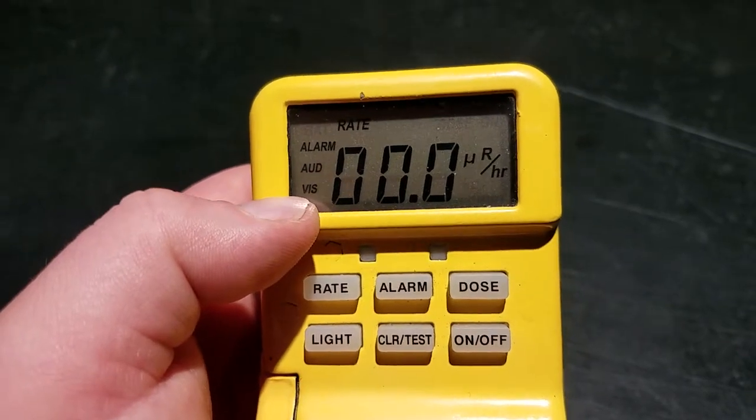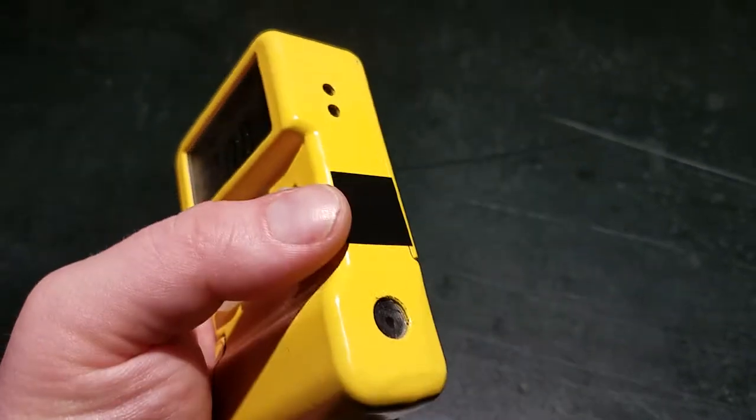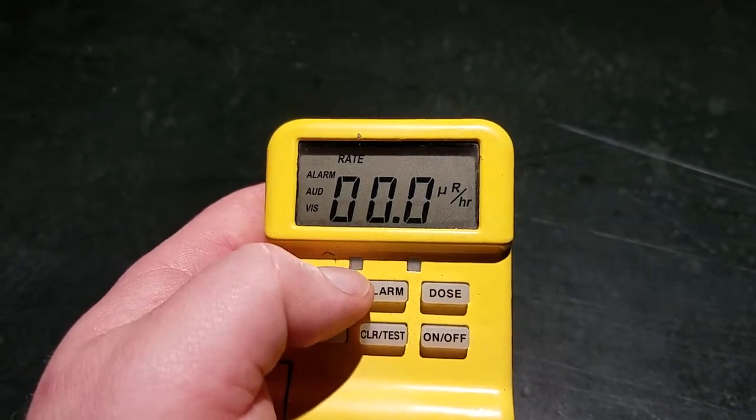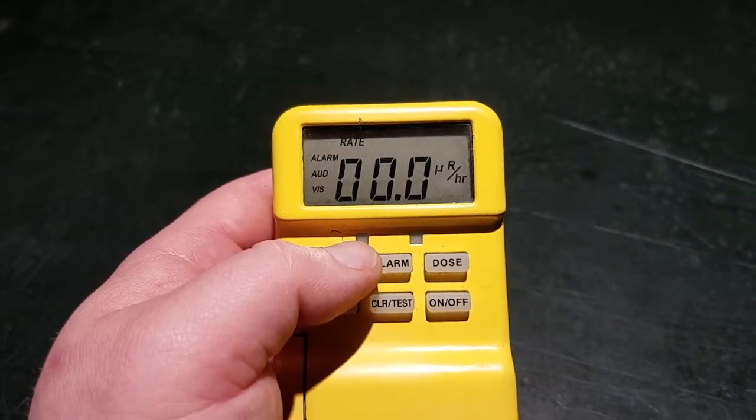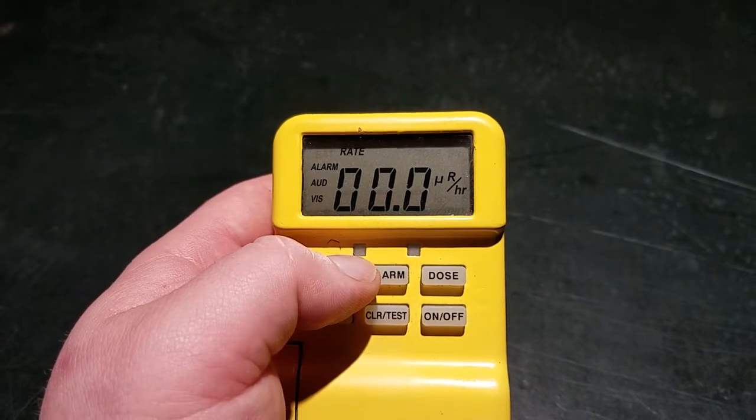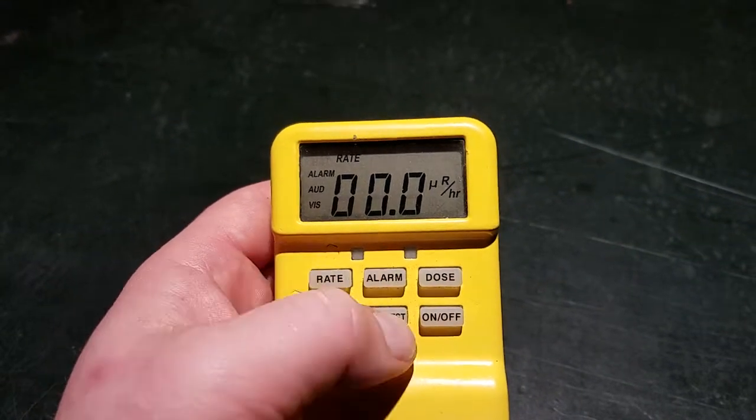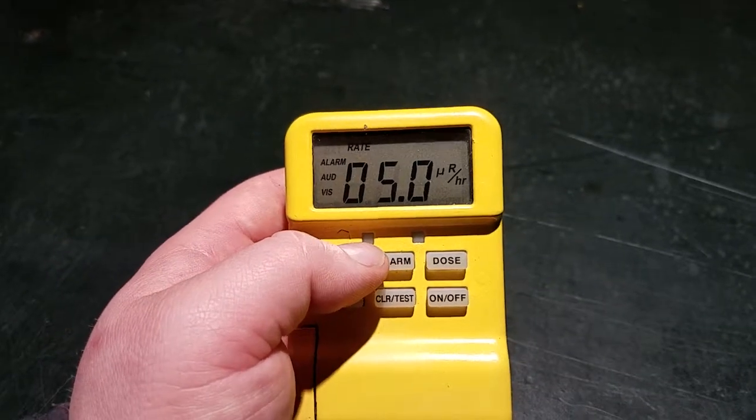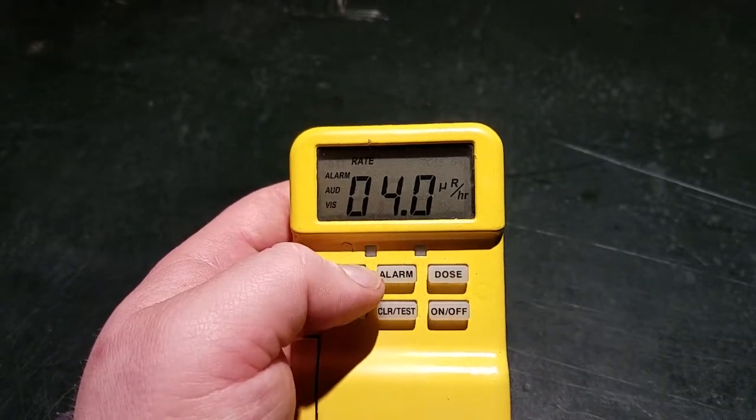The audible alarms will be beeps, and the visual alarms here on the left are for the rate. This will actually flash green if it hits the low threshold and start beeping. You can hit the clear button and it'll stop beeping, but if you hit the upper threshold for rate, it'll go red and the beeping will not stop even if you hit clear.